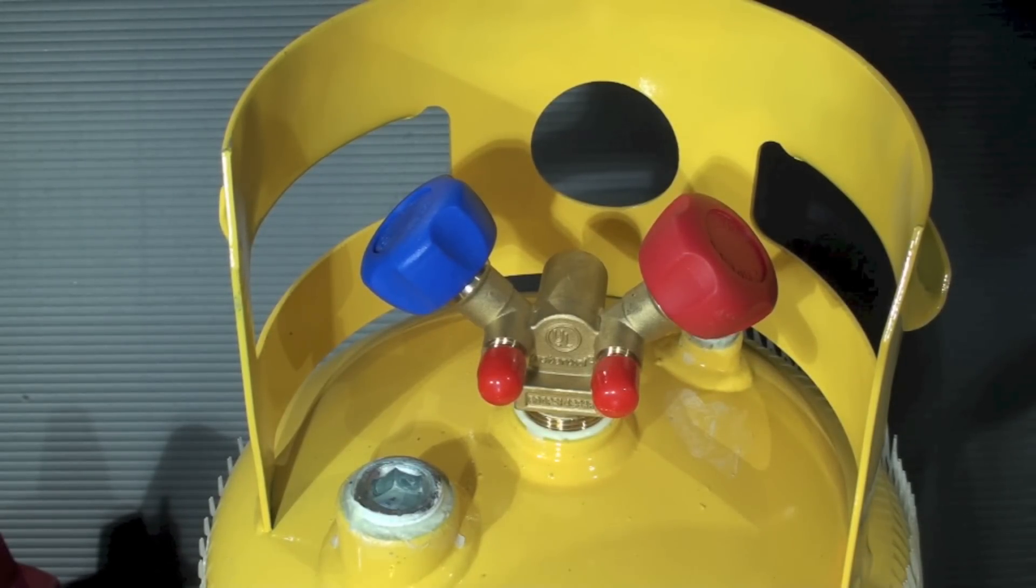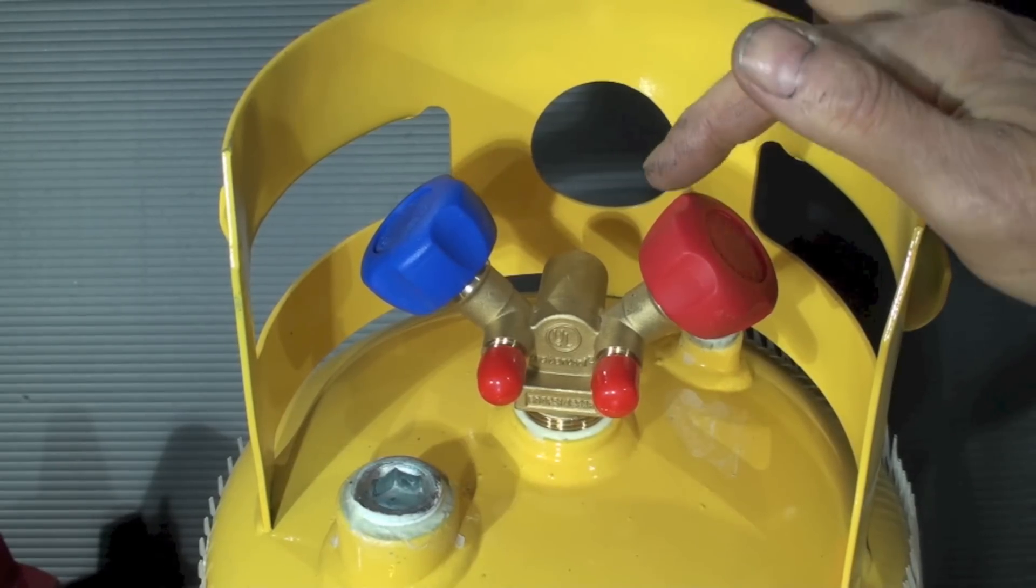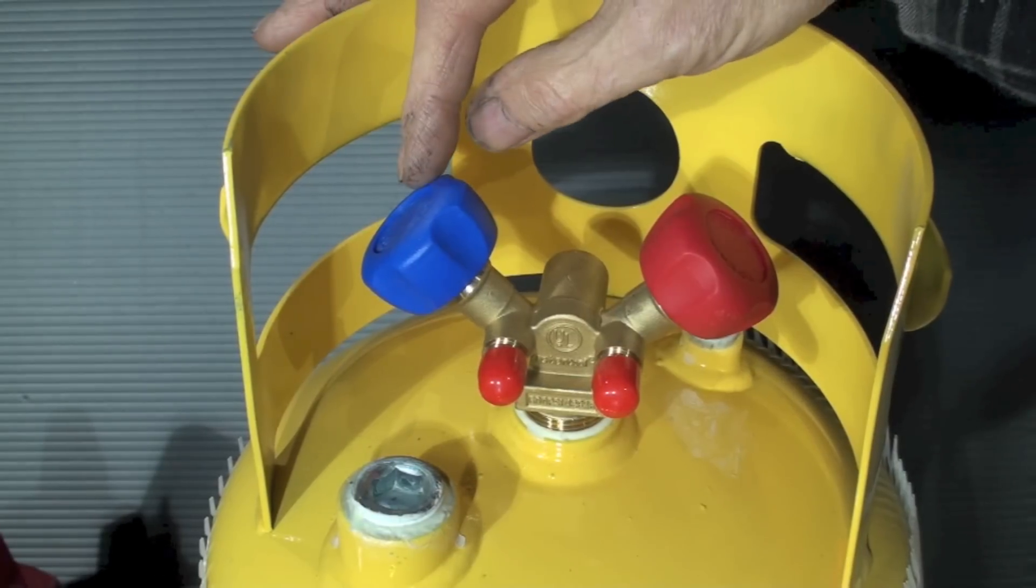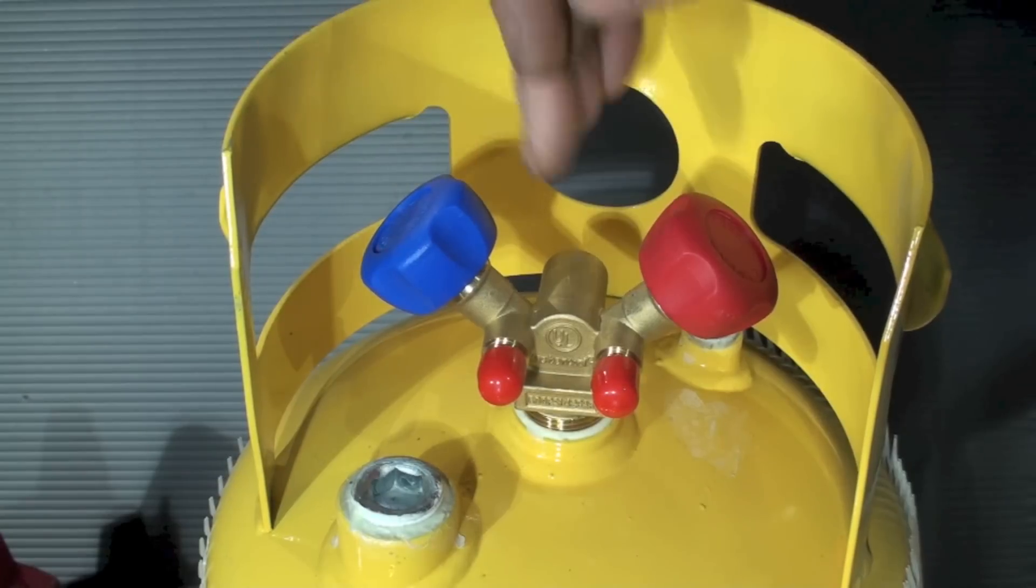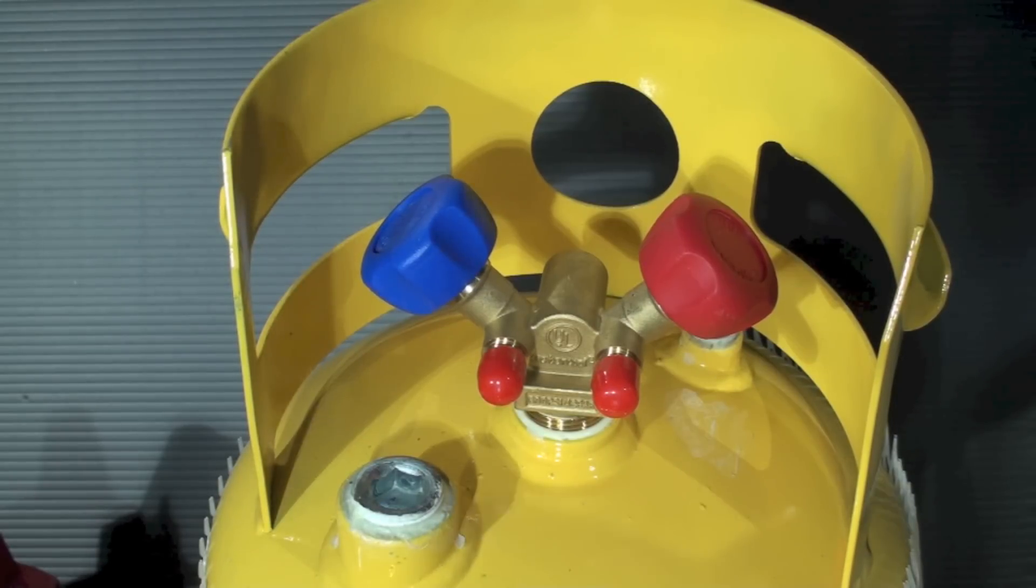If you want to pull liquid out of it, you would open the liquid line. This is the liquid line—it's red. That's the gas line—it's blue. So the gas line is going to go to the top and the liquid line is going to go to the bottom. Now this color code, I'm not sure they're still doing it, but one manufacturer used red for liquid and the other manufacturer used blue for liquid, so you can't really count on the color code.